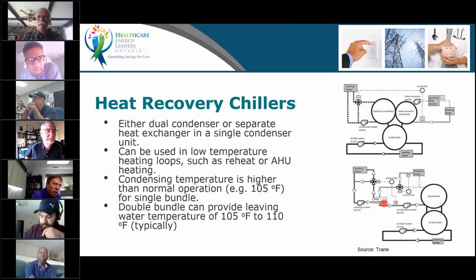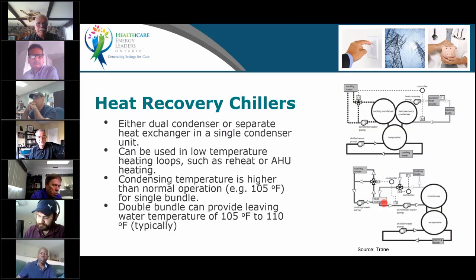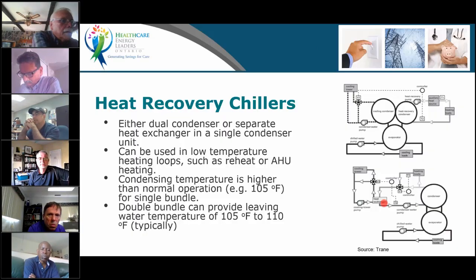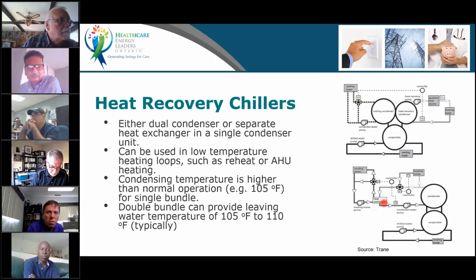And I'll just add, if you've got your CHP rejecting heat in the middle of the summer and you've got a heat reclaim chiller running, maybe you want to think about running one of your more efficient conventional centrifugals. Use your heat rejected from the CHP to take care of your reheat, your low temp heating. Shut that heat reclaim chiller off or unload it. But then the flip side of that is in the middle of the winter, when you need a lot of heating, run that heat reclaim chiller, let it do as much as it can on the heat recovery side, and then use the CHP for the medium and high grade heat. Just maybe opposite to what you were thinking.